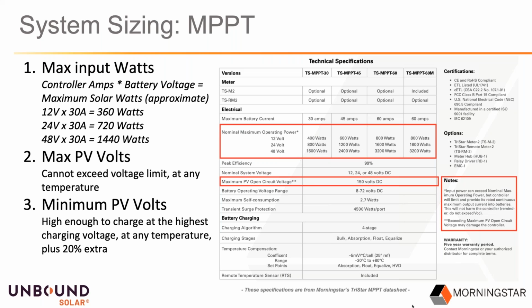But in the case of Morningstar, it's going to be able to handle an overload and just limit that output. The second thing we're going to look at is the max PV volts, which is really key because we can't exceed this under any circumstances, or it'll damage the controller. In this case, the TriStar MPPT controllers are rated for 150 volts. There's another set of TriStar controllers that's rated for 600 volts, which is what we'd use if you had really long wire runs or long distance from your PV array to the battery. So we need to design a system that will never go over this 150 volts DC.